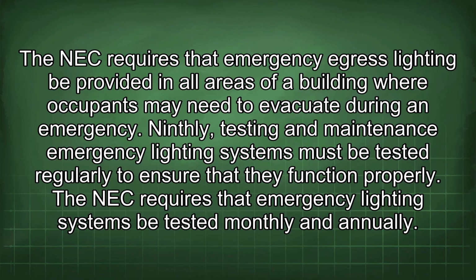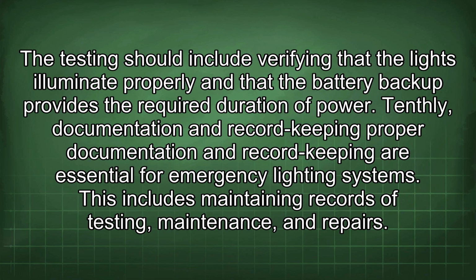Emergency lighting systems must be tested regularly to ensure that they function properly. The NEC requires that emergency lighting systems be tested monthly and annually. The testing should include verifying that the lights illuminate properly and that the battery backup provides the required duration of power. Tenthly, documentation and record keeping.